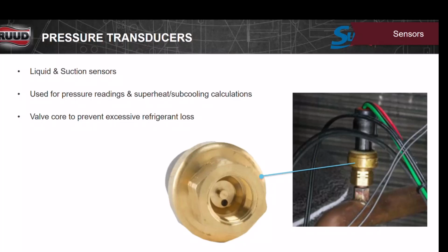Some of the things that I've run into at least one time in my career with these units, we had a compressor that we were on our second compressor, fixing to be third. We kept losing compressors. Every time we would go out there, everything seems to be running fine. So I got called out to the job because he said, man, we're fixing to lose this compressor. So I got back out there. We started looking. First thing I started doing was looking at the pressure transducers and the thermistors. I found that the suction transducer on the indoor evaporator coil said that the pressure was 97 pounds pressure. My gauge said it was 154 pounds. I'm like, what's going on here?